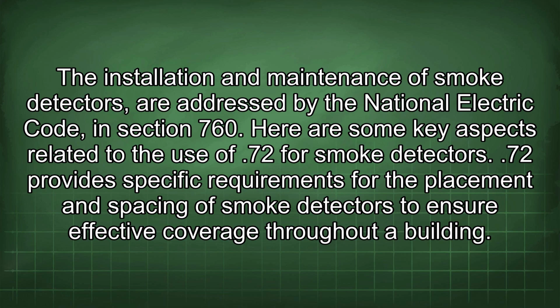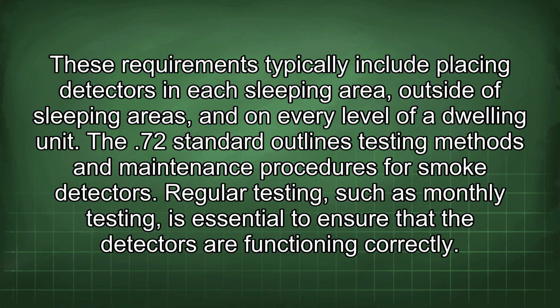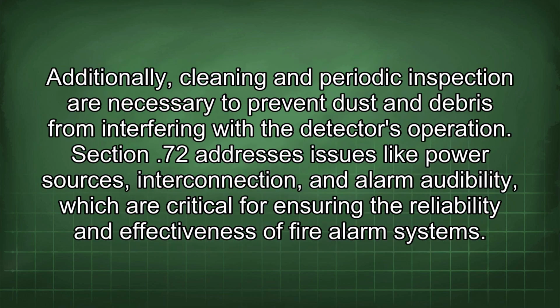Here are some key aspects related to the use of NFPA 72 for smoke detectors. NFPA 72 provides specific requirements for the placement and spacing of smoke detectors to ensure effective coverage throughout a building. These requirements typically include placing detectors in each sleeping area, outside of sleeping areas, and on every level of a dwelling unit. The NFPA 72 standard outlines testing methods and maintenance procedures for smoke detectors. Regular testing, such as monthly testing, is essential to ensure that the detectors are functioning correctly. Additionally, cleaning and periodic inspection are necessary to prevent dust and debris from interfering with the detector's operation.